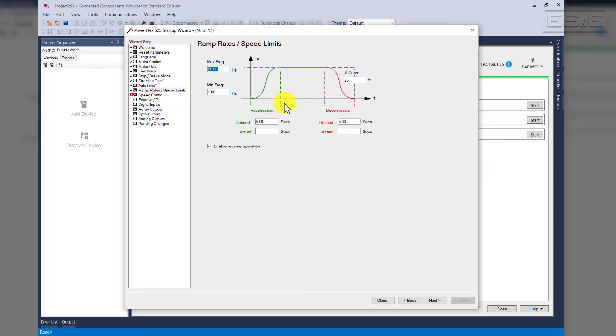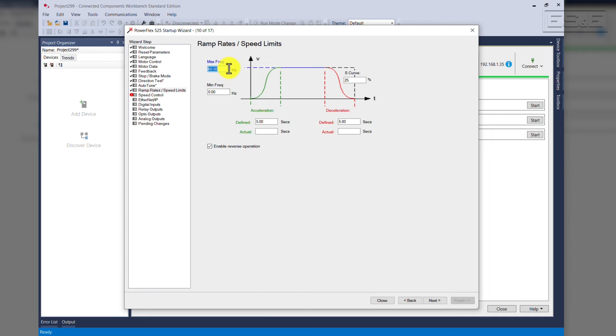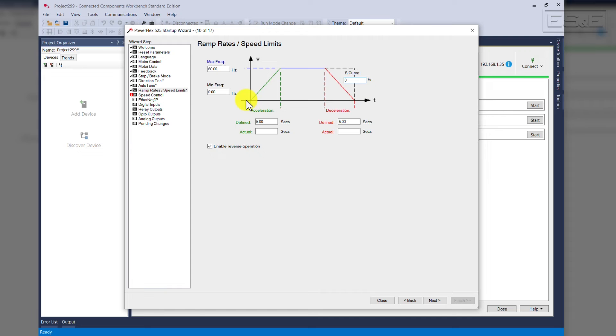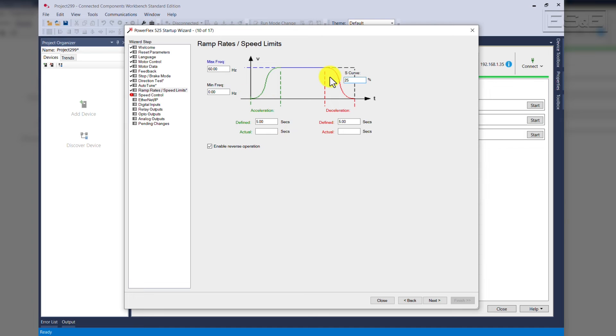The ramp rates and speed limits. The min frequency is zero hertz, our max frequency is 60 hertz. This is where we set our decel and accel, and also the S-curve. Please note the S-curve is zero, it's a very straight line when you're accelerating and decelerating. When you add S-curve, it actually softens that. We'll press Next.